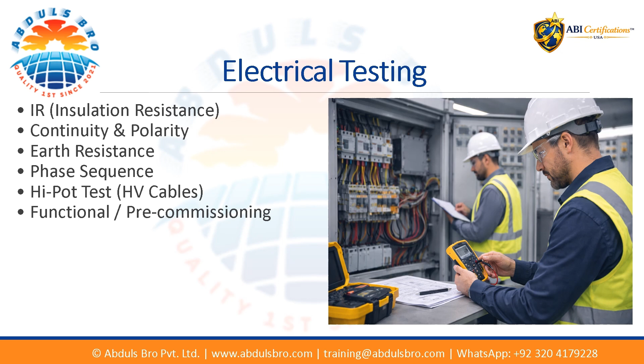Next is electrical testing. Electrical QAQC includes multiple tests before energization. IR test checks insulation quality. Continuity and polarity ensure correct connections. Earth resistance ensures safe grounding. Phase sequence is critical for motor rotation. For high voltage systems, hi-pot testing is performed. Finally, functional testing confirms system readiness.